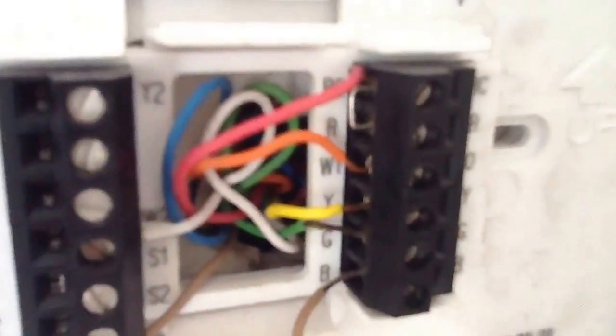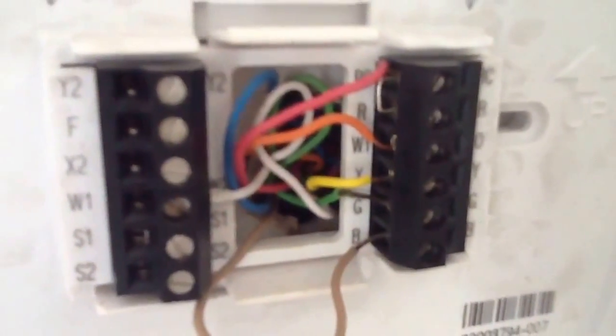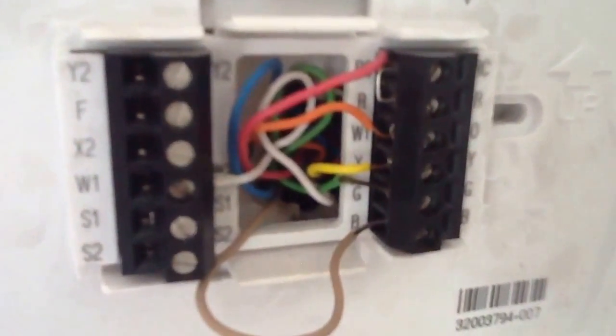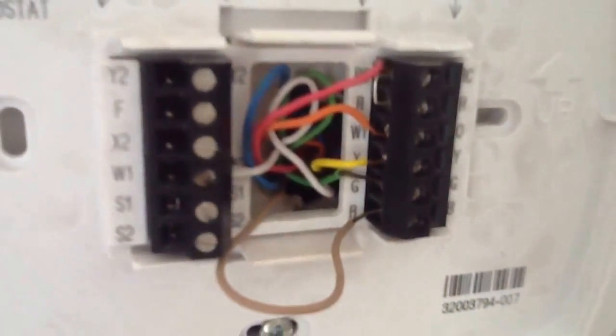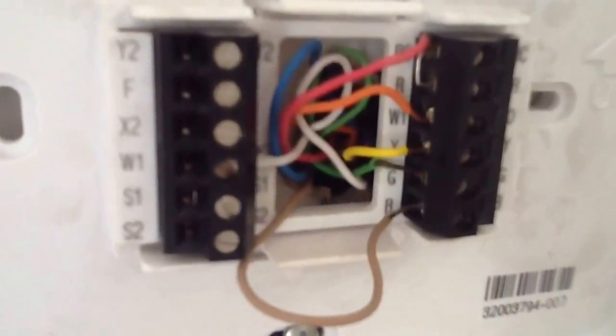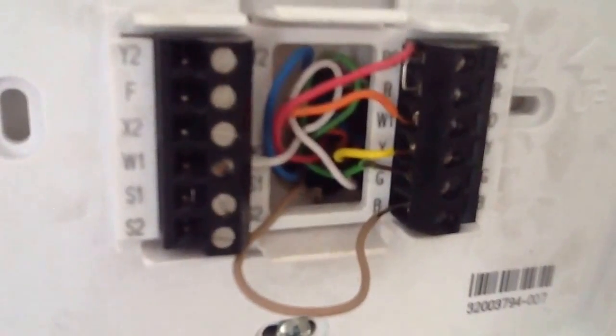The red wire is tied in with the RC and RH. The orange wire is O, which is your reversing valve. Y is yellow, which is your compressor — that will energize on both heat and cool. G is your green wire, which is your fan. In this particular case, B is a common terminal on the thermostat.